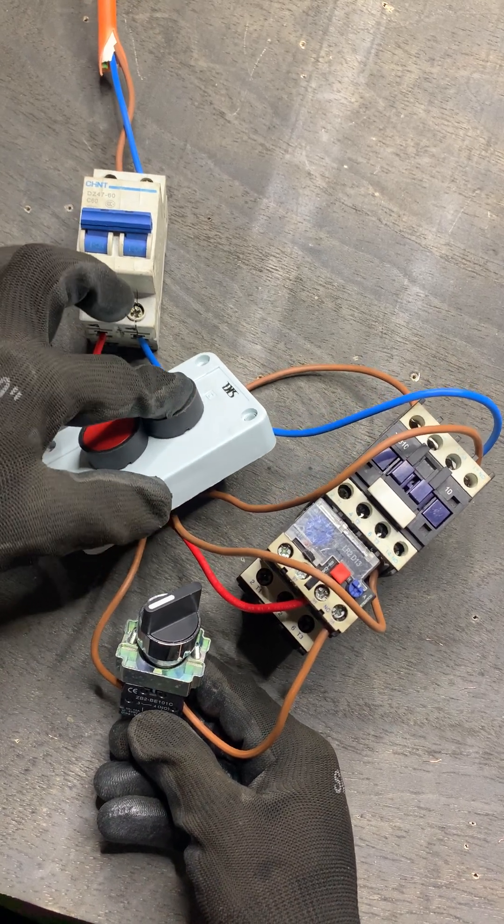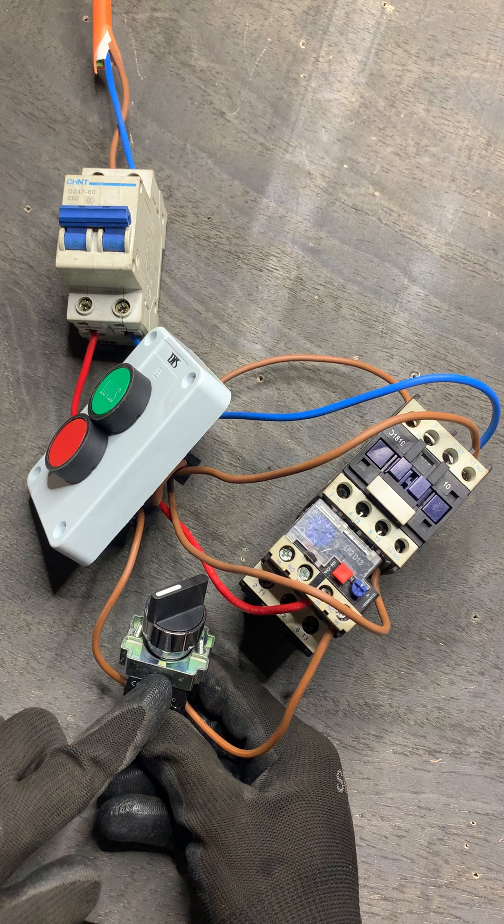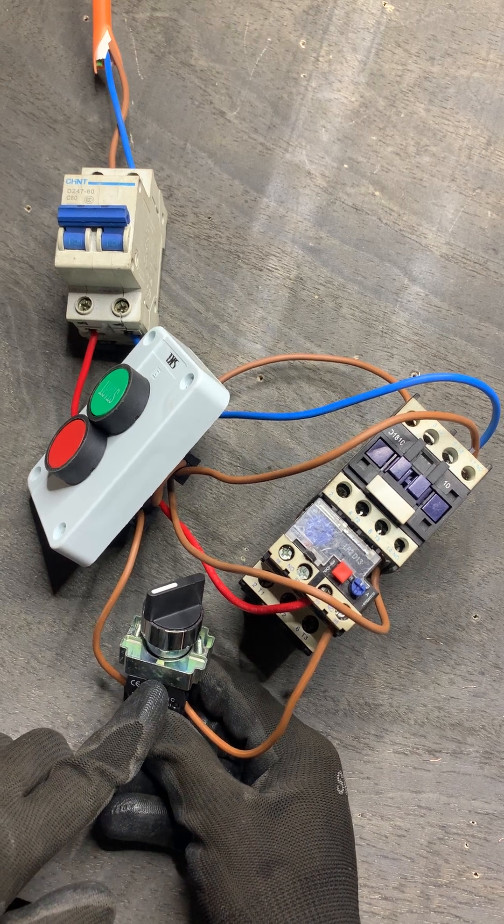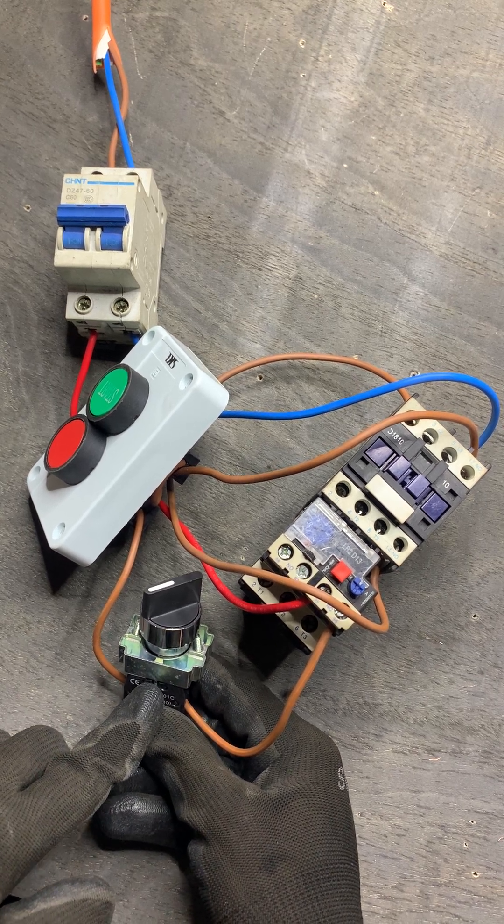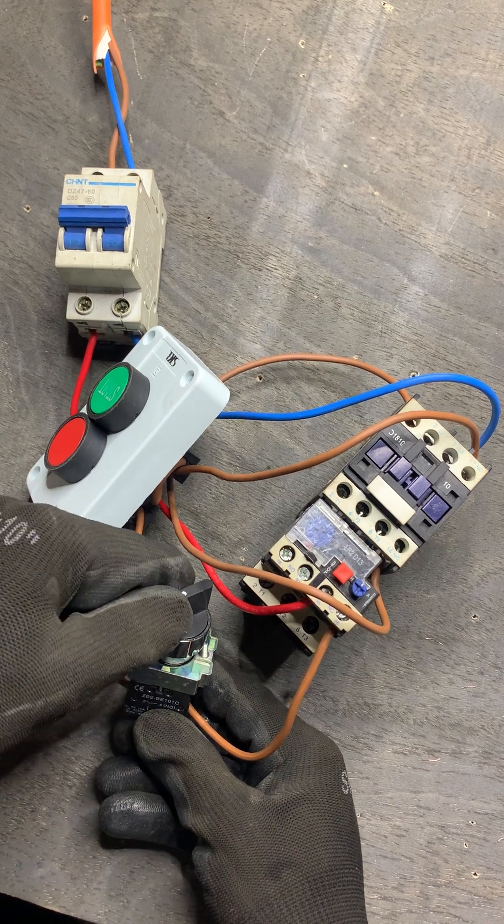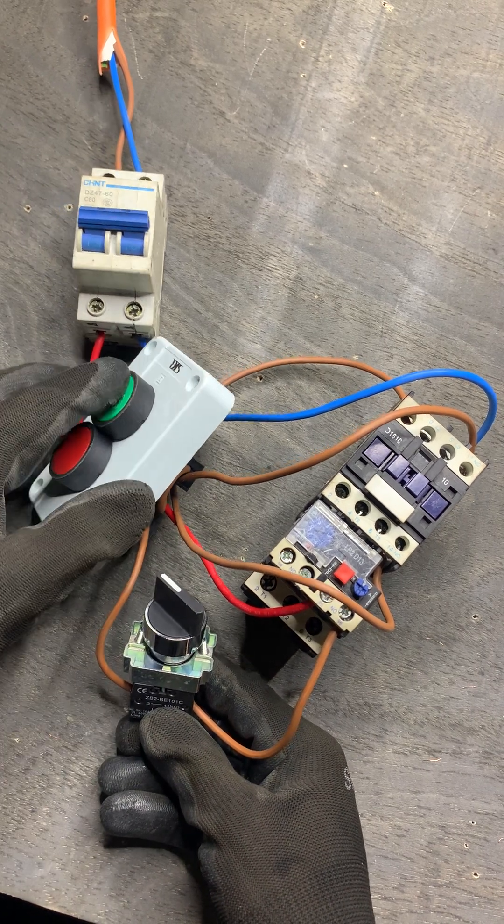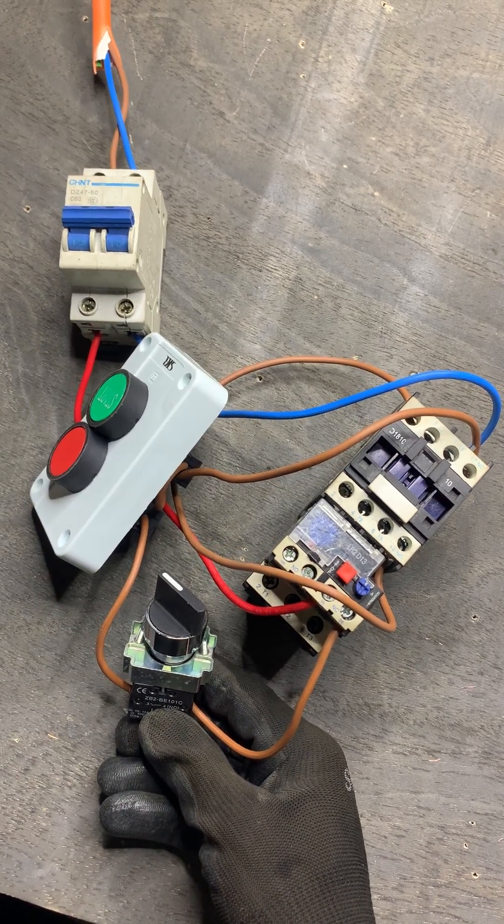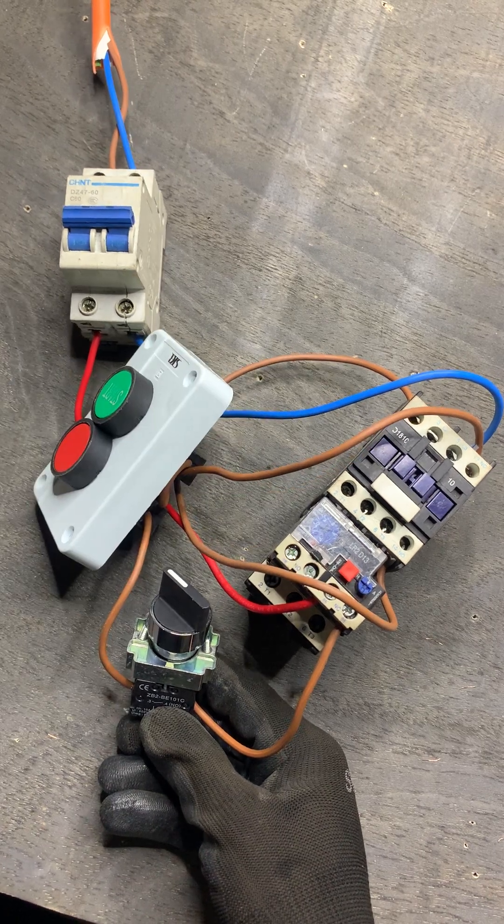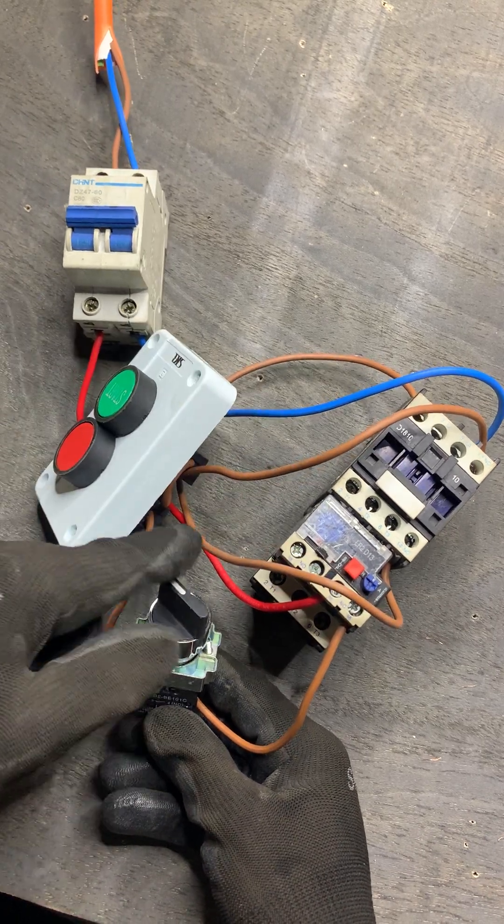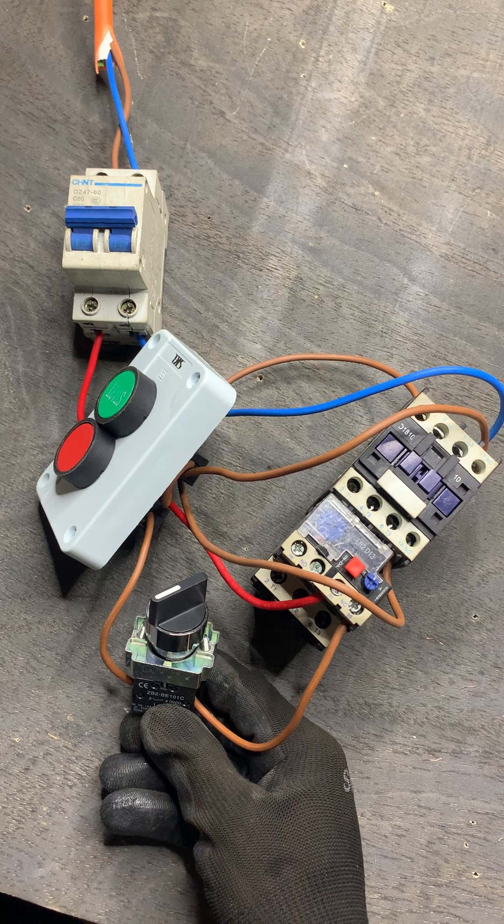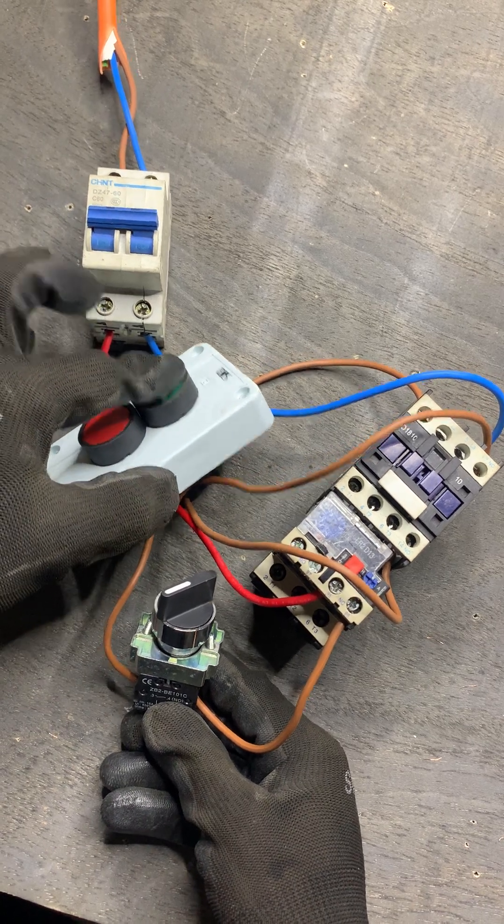Why? Because the selector switch works like an emergency push button. So unless I rotate it again before I press on the start button, it will not work. I need to press on the stop button before it will work. If I rotate it, it will not work again.